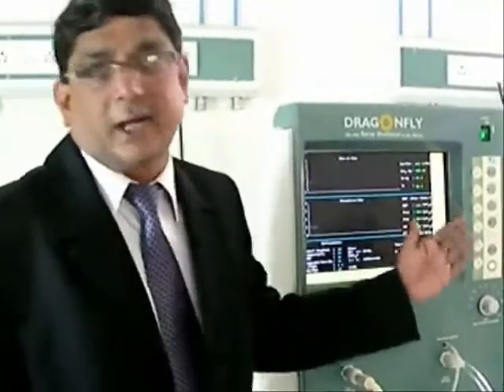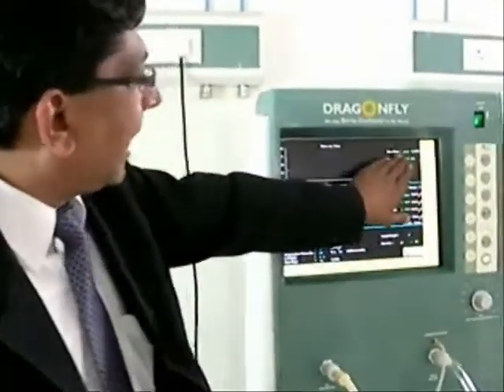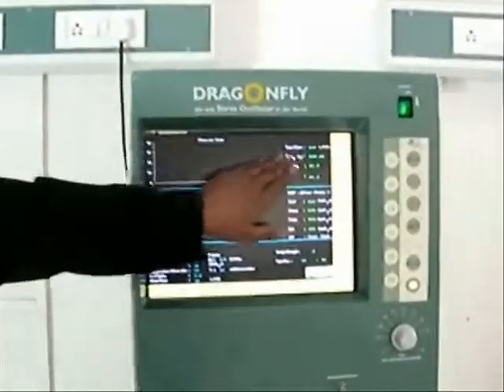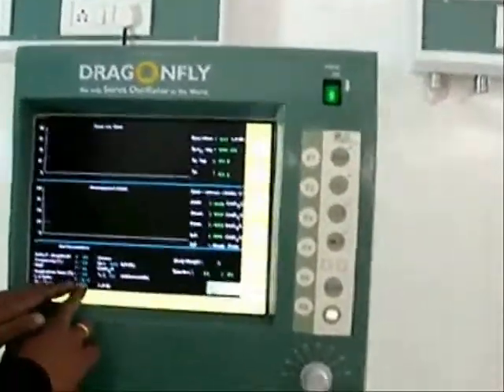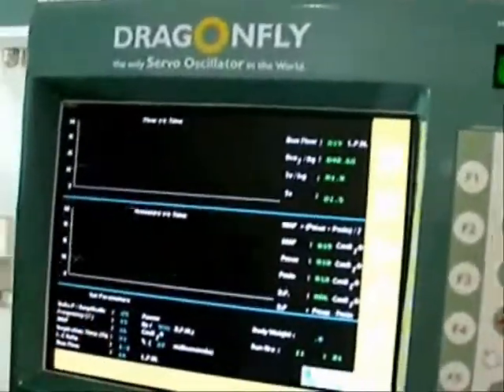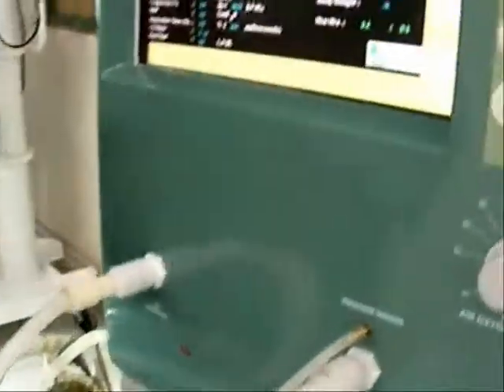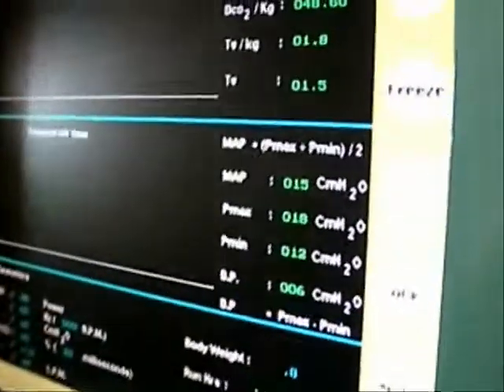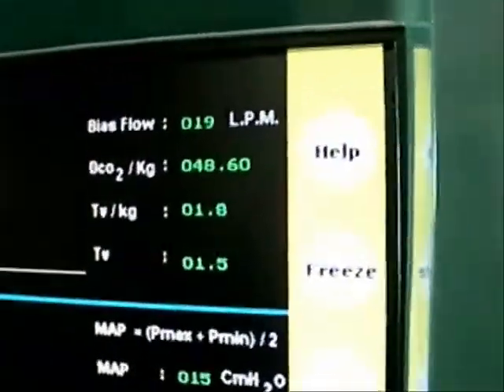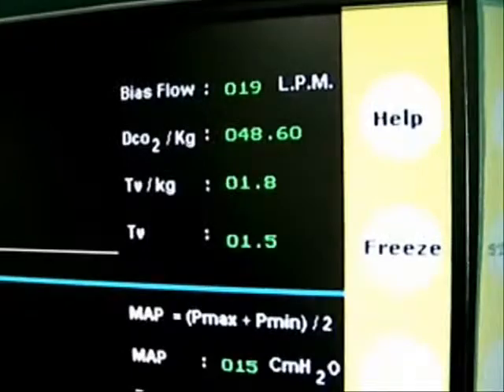and that is one of the features of the Dragonfly. Again, you can notice that the bias flow is automatically adjusted on this. All I have done is just set the mean airway pressure. As explained earlier, the flow and the pressure valve go hand in hand. They have a handshaking mechanism in them. So they talk to each other in electronic language, and they give feedback.